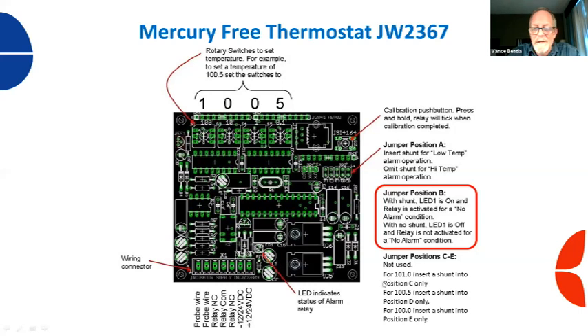I want to talk real quick about the older thermostat. Some of you may still be running it, so we'll just touch on that. You only have three temperature selections. If you put a jumper on C, your temperature set point is 101. This is what we recommend for platinum incubators. If you put it on D, your temperature set point is 100.5, which is what we recommend for platinum hatchers. And then you also have one more selection. If you put it in the E position, it'd be 100 degrees.